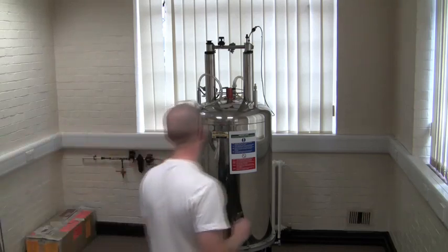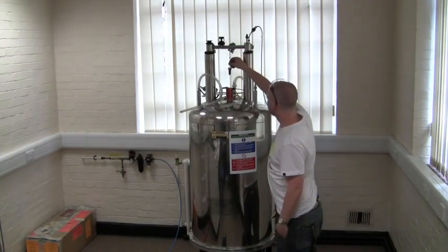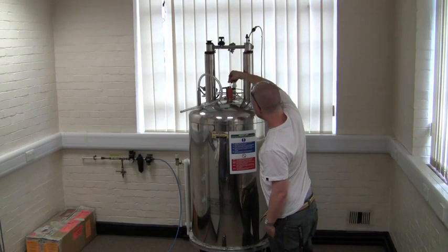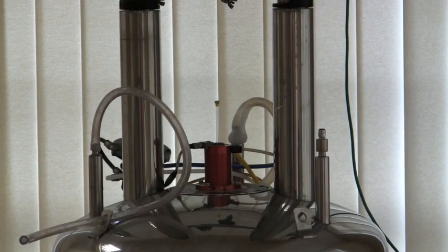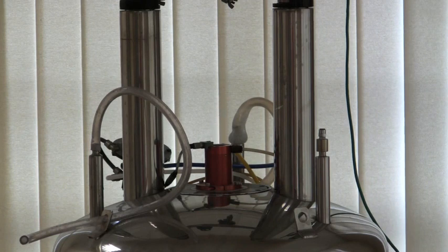The sample in the spinner is placed in the instrument above the magnet and lowered into the magnetic field on a cushion of compressed air. Once the sample has been lowered into the spectrometer, the spectral acquisition can be initiated.